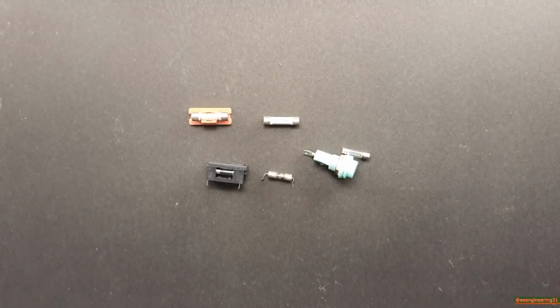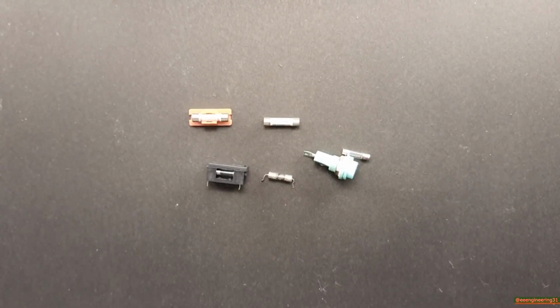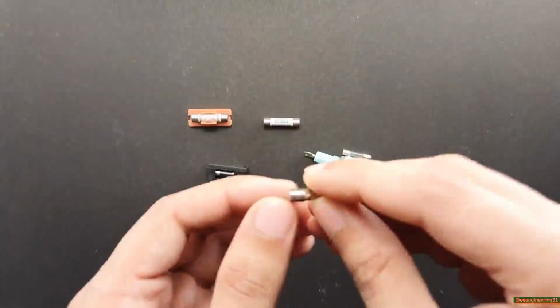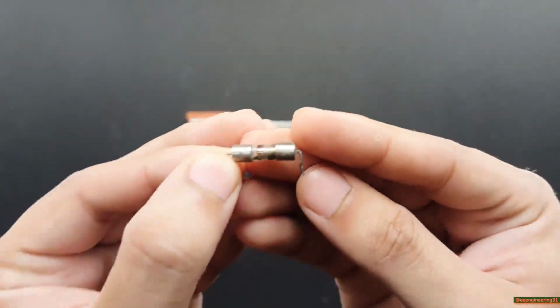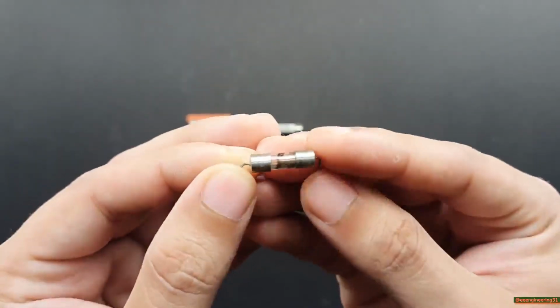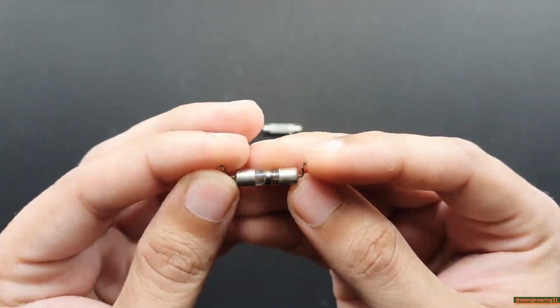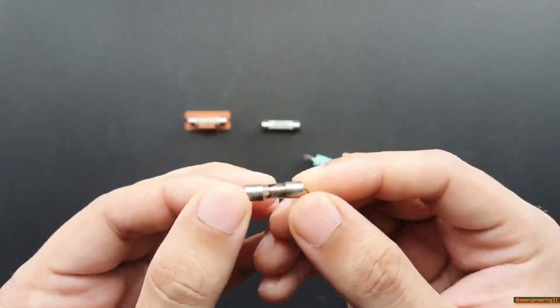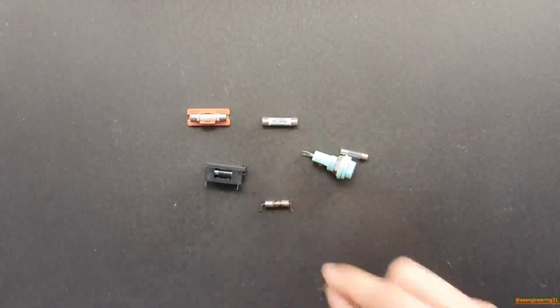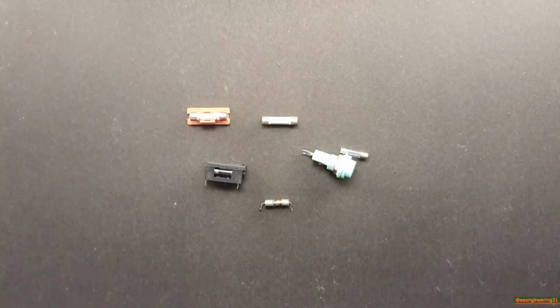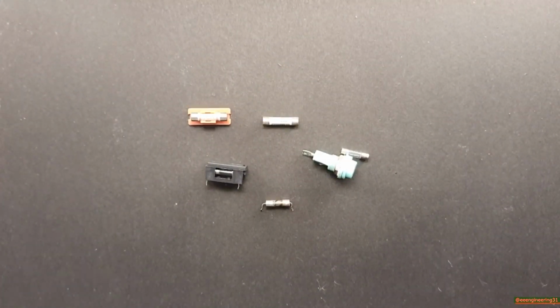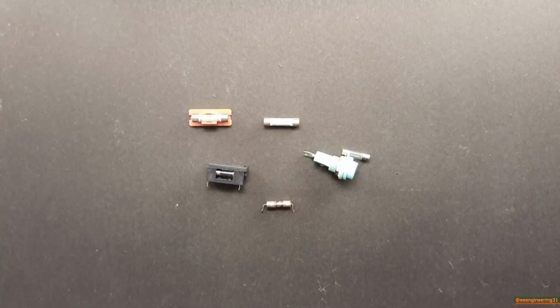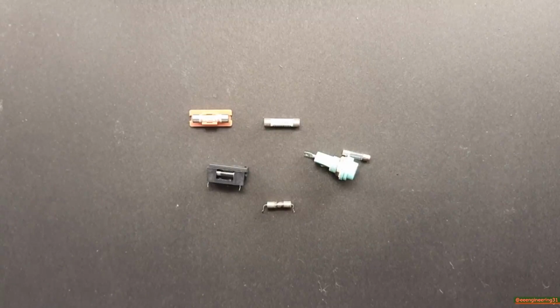If you see a white gap between the wires and black spots inside of the glass, like this case, the fuse blew hard, indicating a lot of current and certain circuit failure. Very rarely, fuses can develop resistance, continuing to pass current but interfering with the full flow.